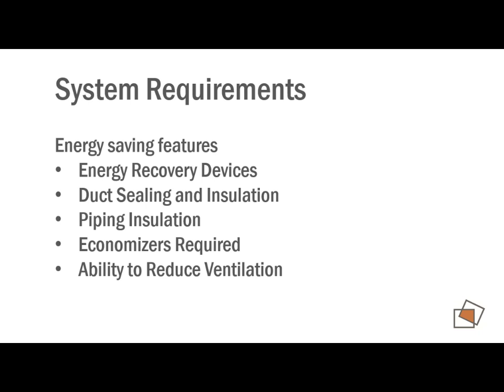In the 2012 code, it requires... does everyone know what an economizer is? The economizer is just a full-size louver so that your air conditioner can bring in 100% outside air to provide cooling for your building when the outside air conditions and the interior space conditions are right. So if we had this room full of people and we're hot and if the weather's like it is outside, it's cool outside, and we got a call for air conditioning, we would just open that louver up and bring air conditioning into the space because it's free cooling, right?